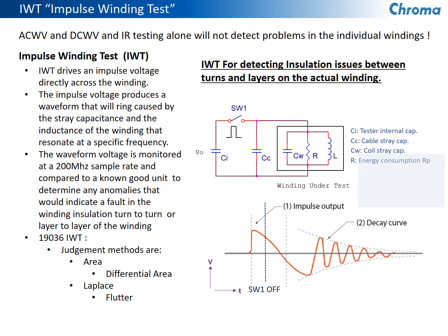After that, you'll see it decay, and while it decays, it'll start to see a ringing. The ringing is caused by stray capacitance or possibly a cable capacitance in parallel with the actual winding. So the inductance of the winding and any stray capacitance will be reflected in a resonant frequency and a ringing waveform like this. Then we look at the data points that make up this waveform, and from there we can do various analysis of the waveform and make judgments based on area, differential area.